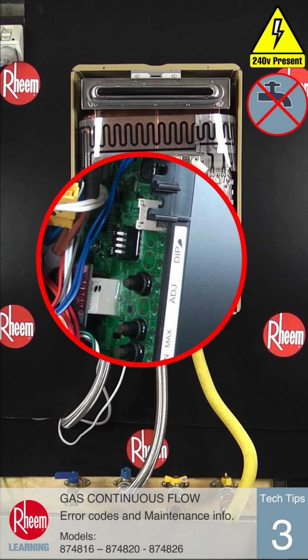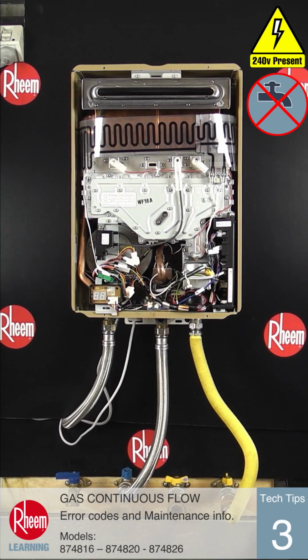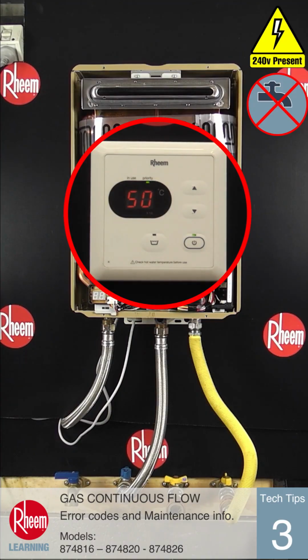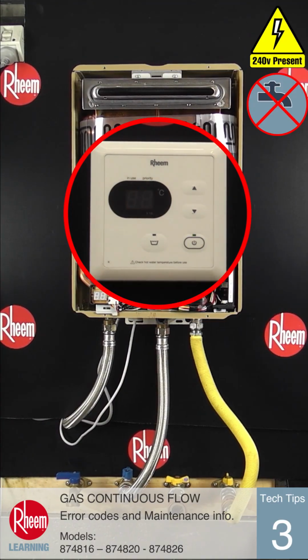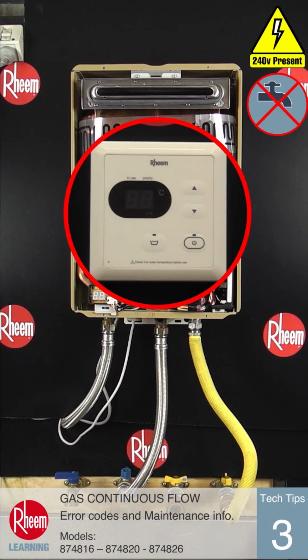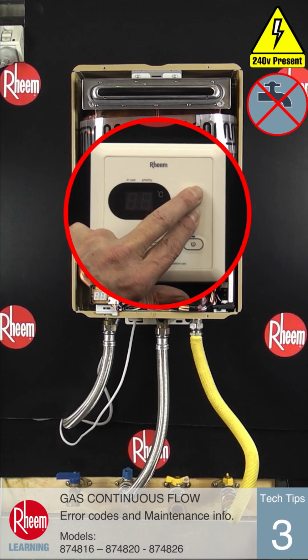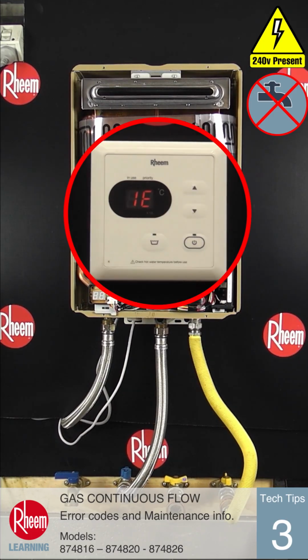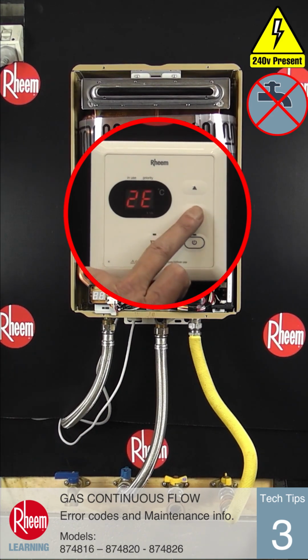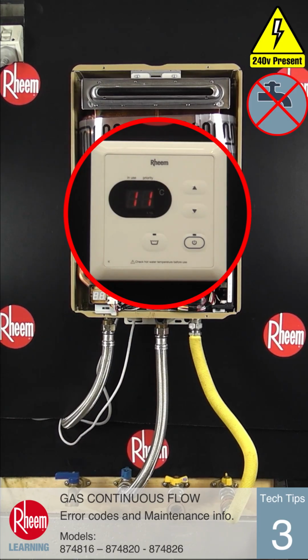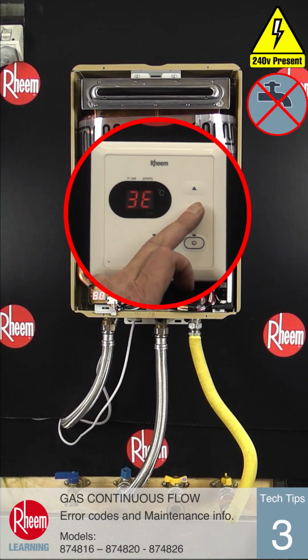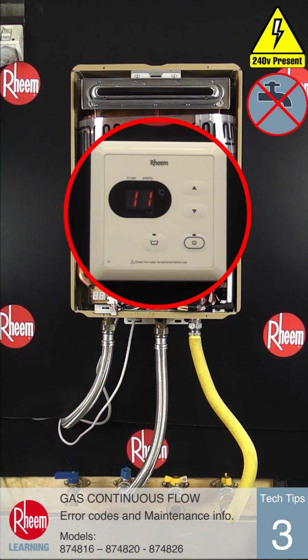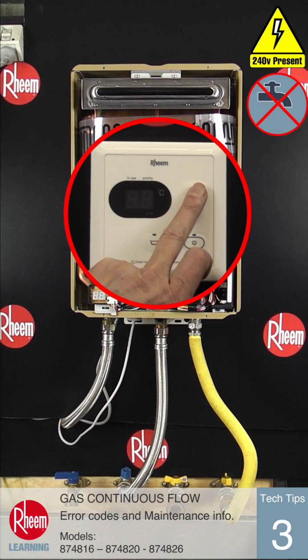This maintenance data is also accessible from wired controllers. Ensure the water heater has power turned on to it. On the temperature controller, press the power button to turn the controller off. Next, press and hold the temperature increase and decrease buttons simultaneously for 3 seconds. As we have seen on the water heater LED display, the controller will now show 1E alternating to a number which is the last error code. The navigation now is the same as we accessed directly from the water heater, this time using the temperature increase and decrease buttons to enter the grid reference.